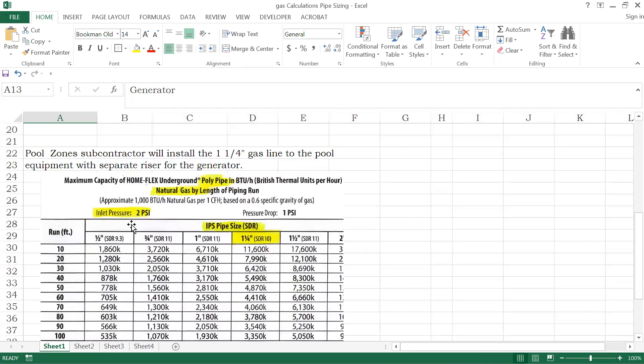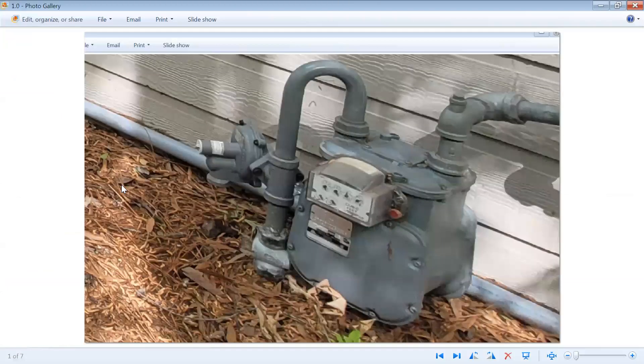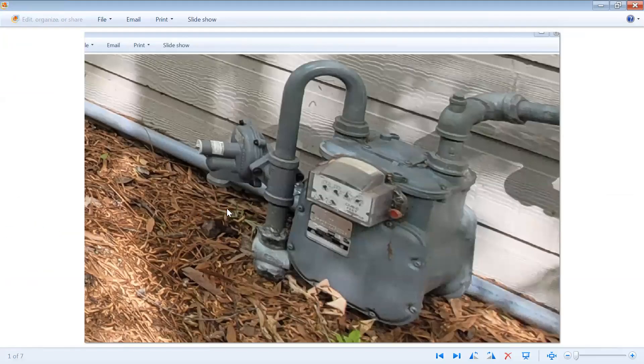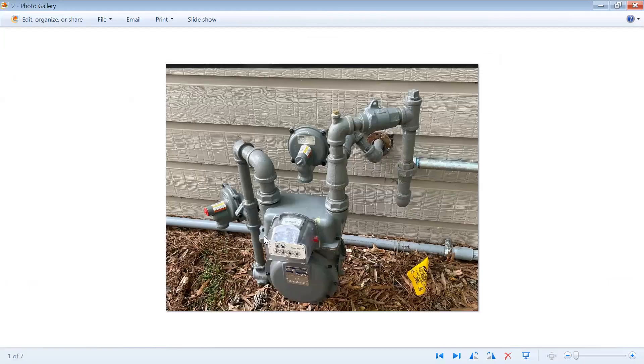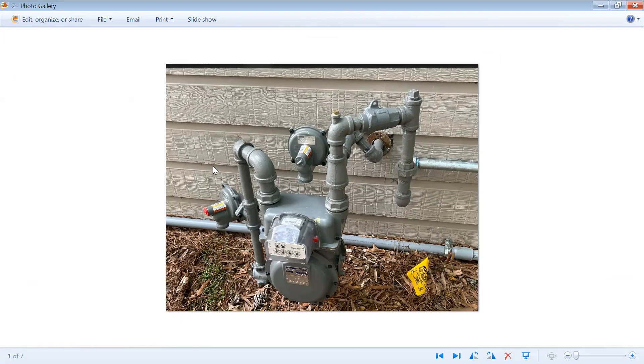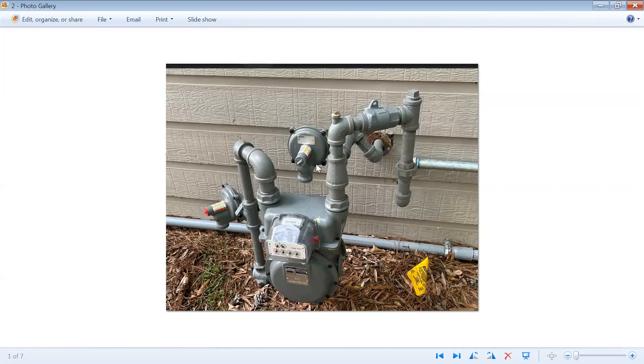This chart is based on the high pressure system with also a pressure drop. We can see two pounds high pressure system. So again it's a very easy idea to understand. Center Point will only run the high pressure lines for the generator and the pool heater outside. It needs to be branched off separately, it will come off its own regulator of two pounds with the red tip, and then the half-pound will be for all of the house appliances.